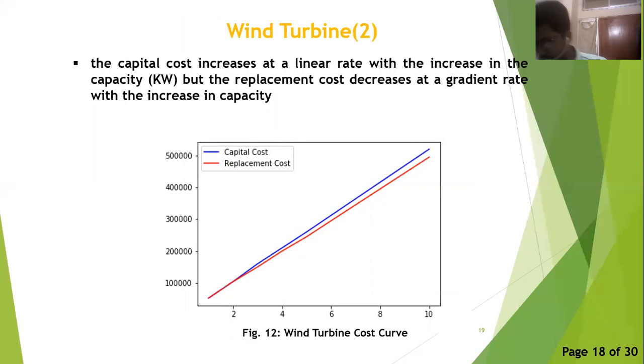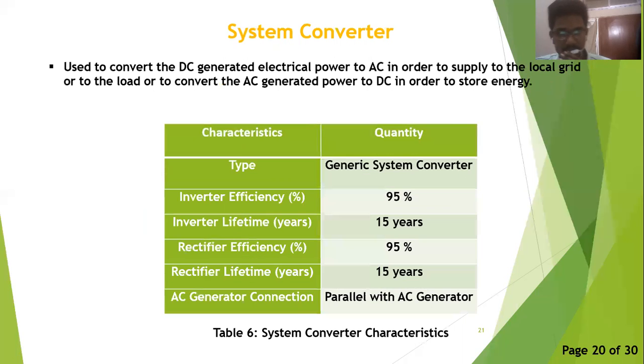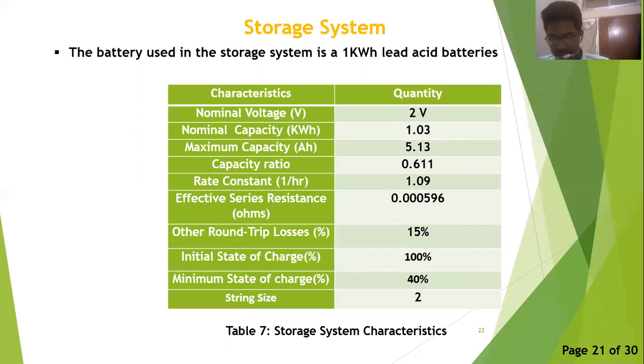The cost curve of the wind turbine is shown in figure 12. The biogas generator used in the system is a generic 500 kW biogas generator with a rated capacity of 500 kW, minimum load ratio of 50%, and a lower heating value of 5.5 MJ/kg. The converter in the system has an efficiency of 95% and is connected in parallel with the AC generator. The battery used in the storage system is a 1 kWh lead-acid battery with a nominal voltage of 2 V, nominal capacity of 1.03 kWh, maximum capacity of 5.13 Ah, minimum state of charge of 40%, and a string size of 2.